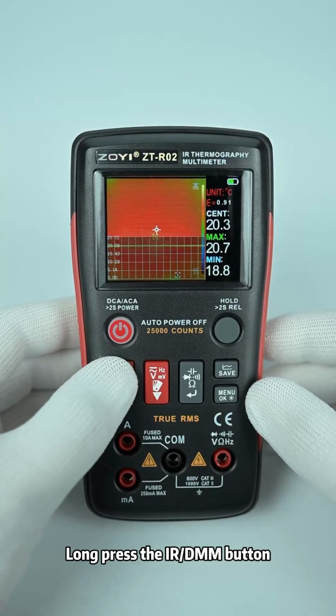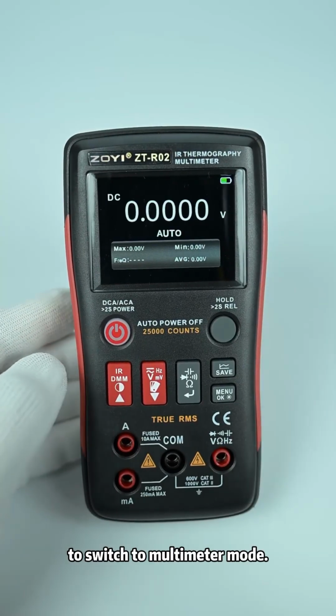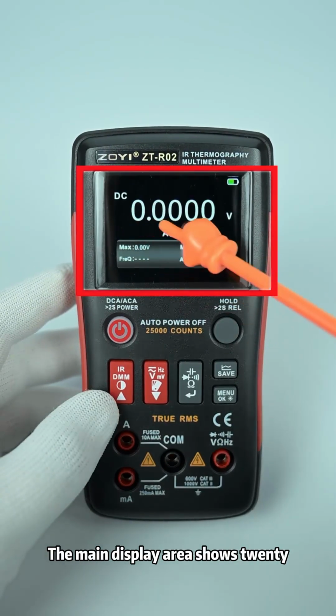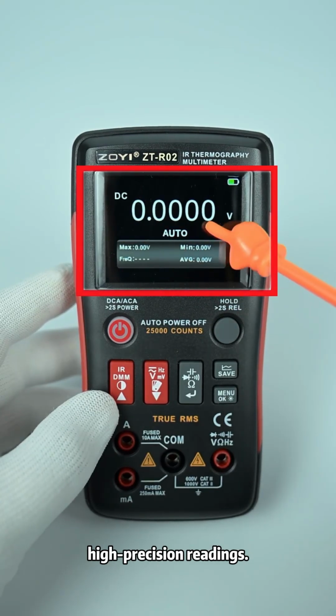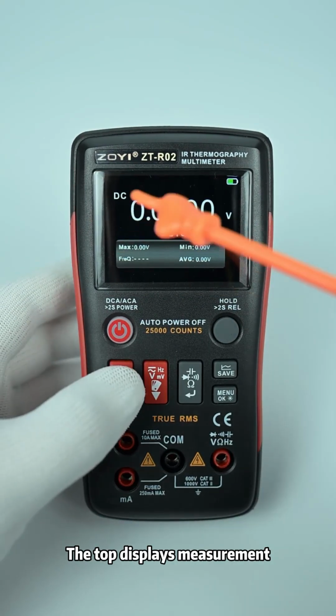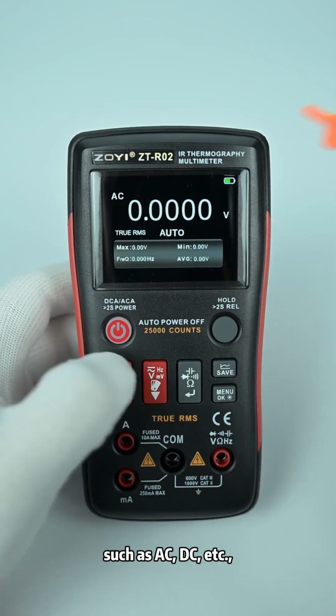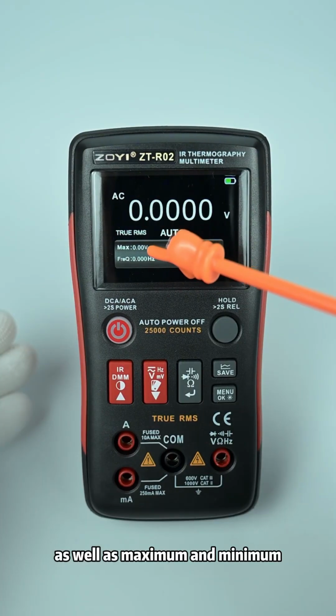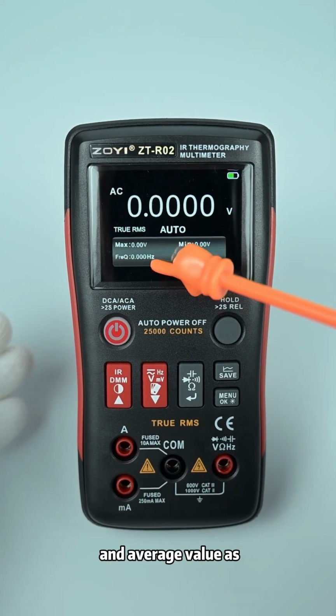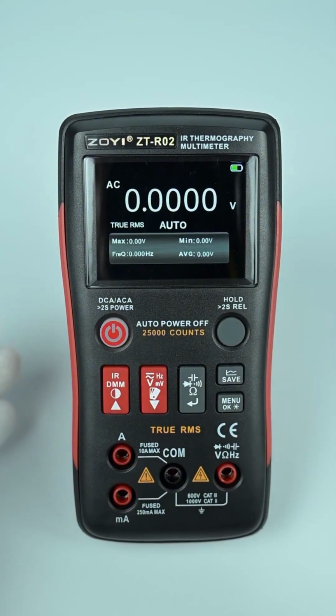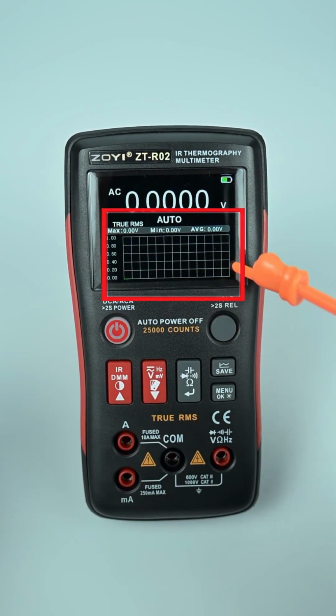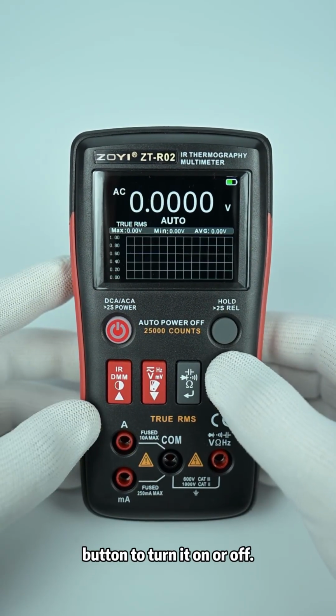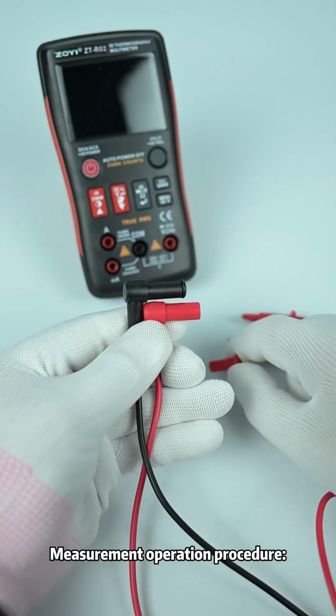Long press the IRDMM button to switch to multimeter mode. The main display area shows 25,000 counts, providing high precision readings. The top displays measurement symbols such as AC, DC, etc., as well as maximum and minimum values, frequency, and average value as secondary readings. Below is the waveform display area, where you can short press the Save button to turn it on or off.